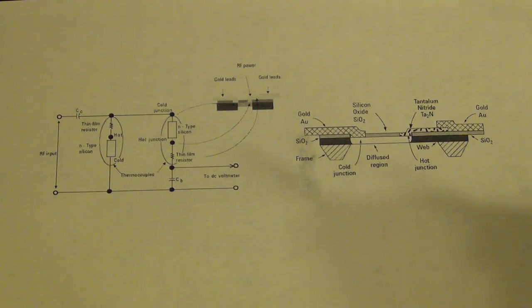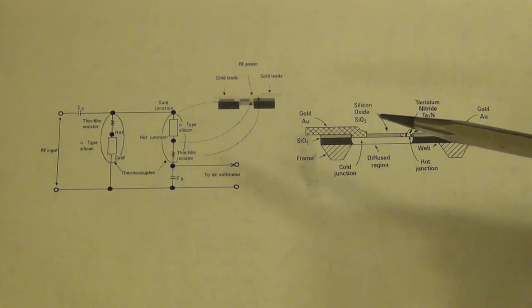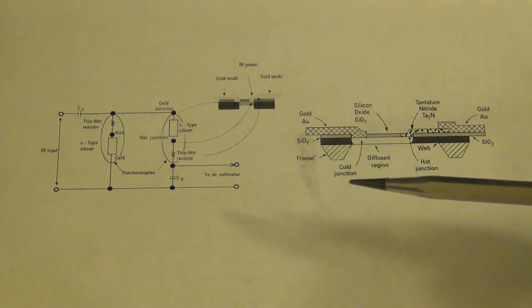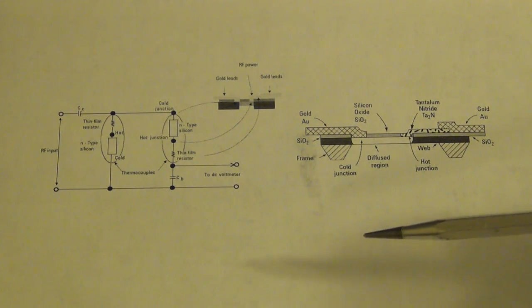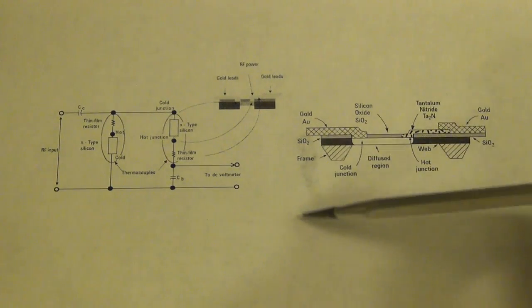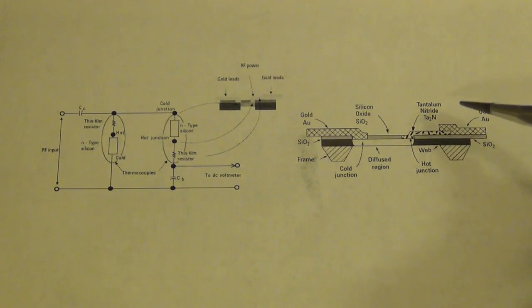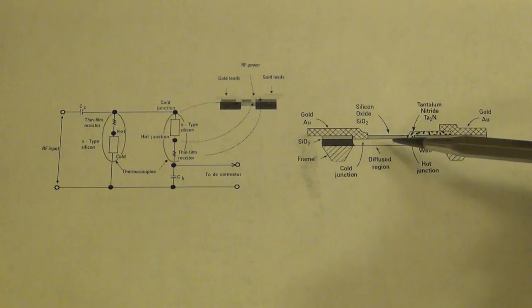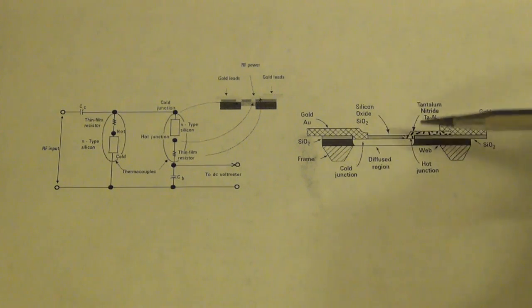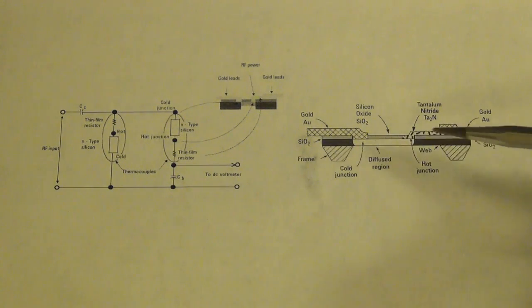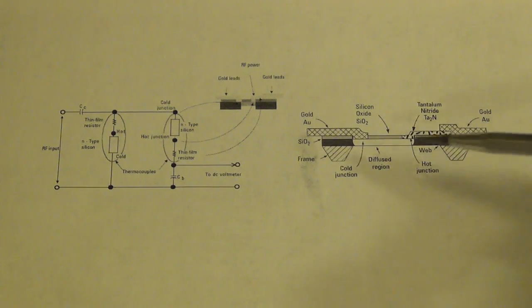So as I said, there were 2 ways of detecting RF power. One was using a thermal temperature effect, and the other one using diodes for rectifying. So here's a special type of semiconductor that uses tantalum nitride on one side, separated by silicon oxide, which when exposed to RF power creates a gradient of temperature, and that gradient of temperature can then be picked up and then amplified and measured.